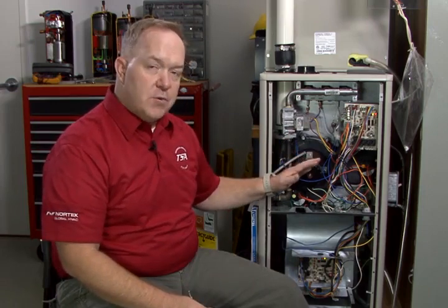like a two-stage variable speed or even a single stage that has possibly been upgraded to variable speed, is the importance of realizing that the control board, during the ignition sequence or through pre-purge, is looking to recognize the blower early in that sequence. Even though the blower will not start, obviously, until the furnace has fired and proven flame, while the furnace is going through the pre-purge sequence, it's going to begin looking right away for the presence of the motor so that it knows that the motor is communicating and it's ready to operate once ignition has taken place.